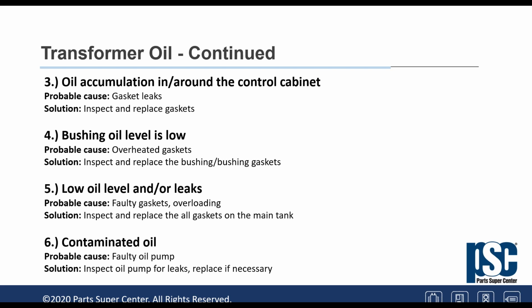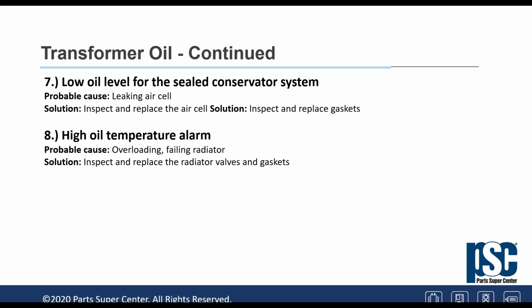Item 6, contaminated oil. Again, what can contaminate the oil? As we said, leaks or infiltration of moisture or other reasons. Also, the age of the oil tells us that something is happening to it. Again, we're going to inspect for oil pump leaks and so forth. Anywhere there are two metal surfaces or a metal and a porcelain surface meeting, there is a gasket, and that's a source of a leak. This is very, very interesting.